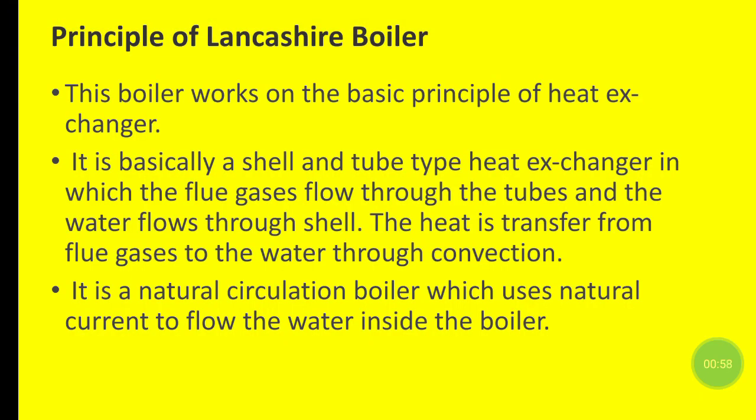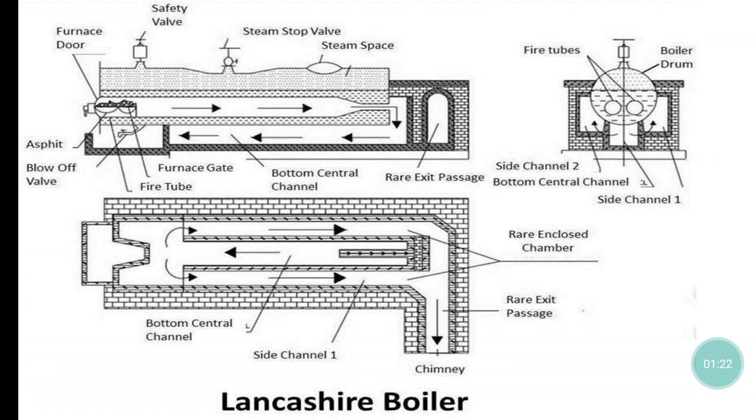Principle of the Lancashire Boiler. This boiler works on the basic principle of a heat exchanger. Actually, in this Lancashire boiler, water absorbs heat from the hot flue gases and then it is converted into steam. It is basically a shell and tube type heat exchanger in which the flue gases flow through the tubes and the water flows through the shell.